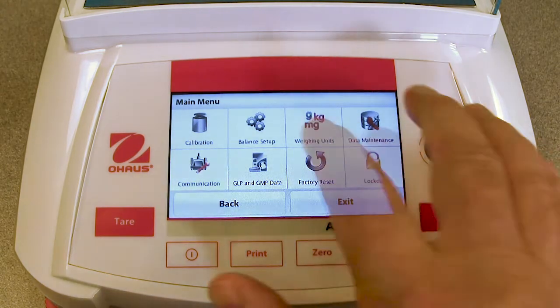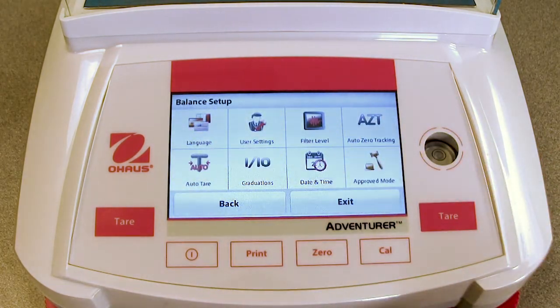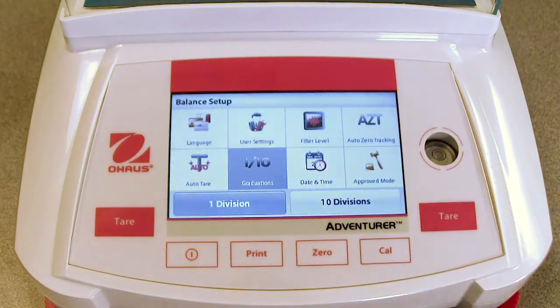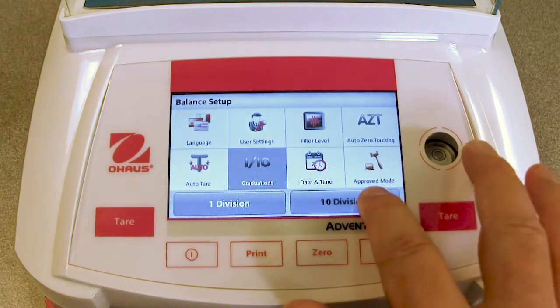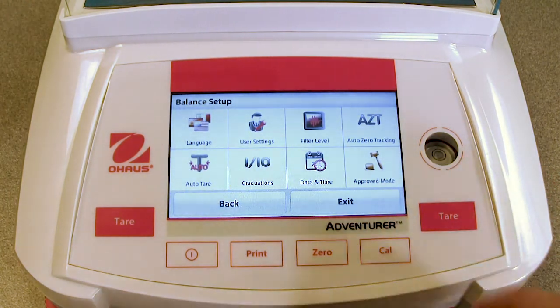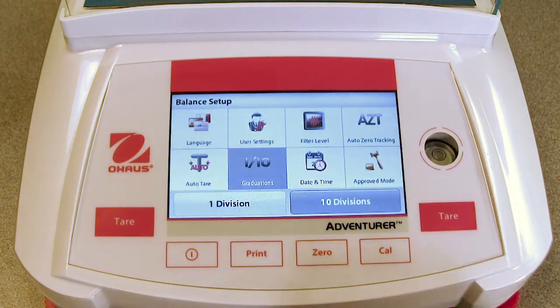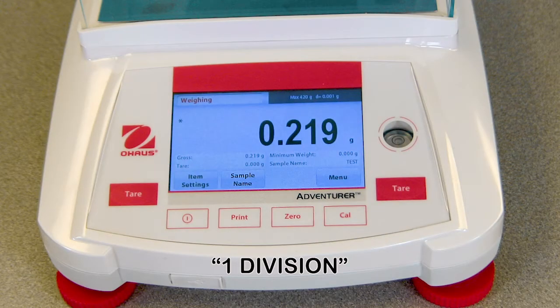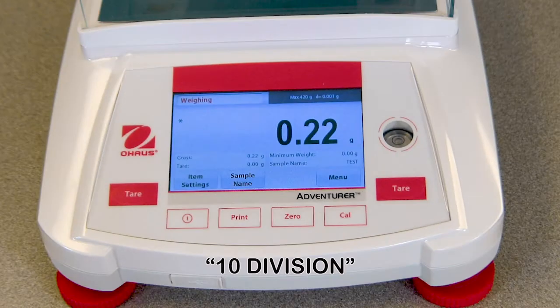The graduations option is used to set the displayed readability of the balance. 10 divisions equals readability is decreased by a factor of 10. 1 division equals standard readability. In this example, the balance is set to 1 division, and the result is 0.219. When changed to 10 division, the result now reads 0.22.